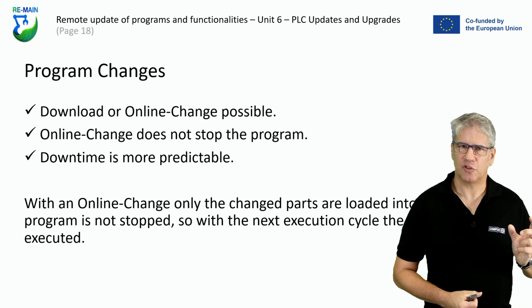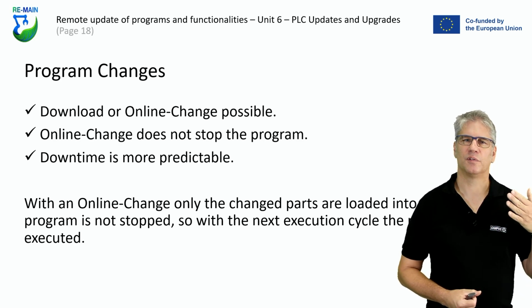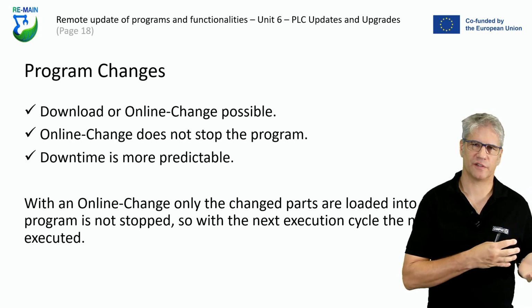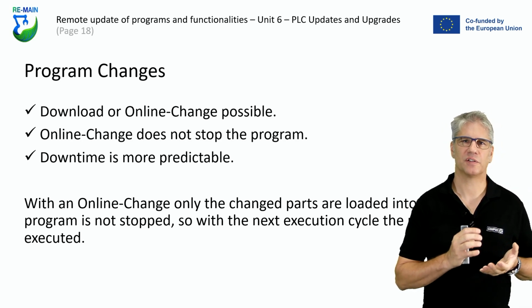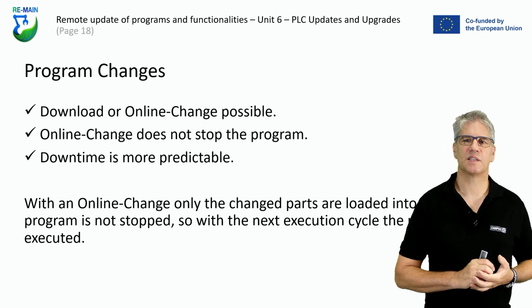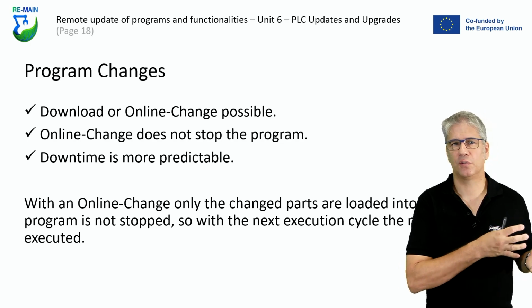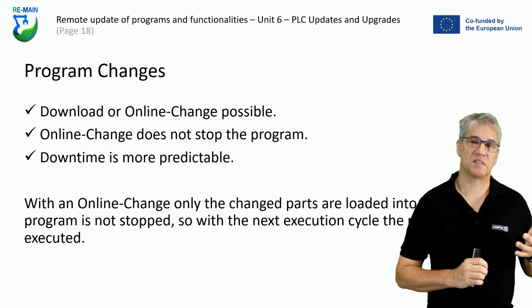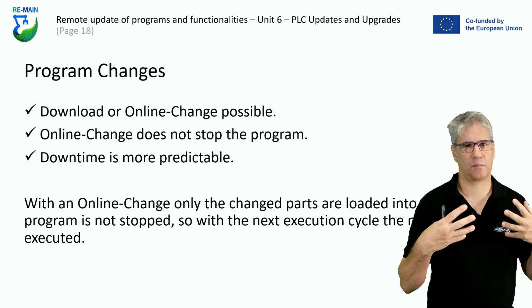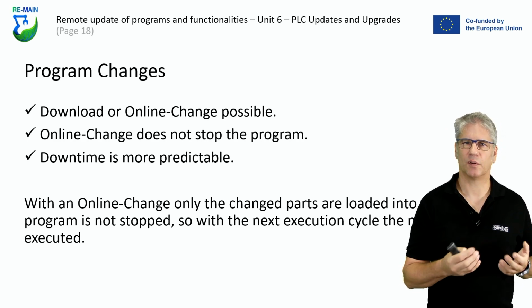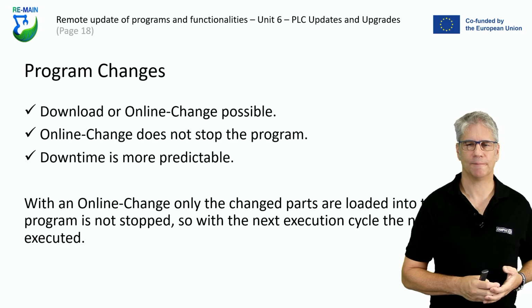And when you just change the program, so introduce a new algorithm, so just some code changes without changing variables, without changing the architecture, the modules, the program components, normally it's possible to do some online change also. You could either do a full download. This is something that most of the PLC manufacturers suggest, because then it's clear that a system is started from scratch, which means that all the variables are initialized properly.